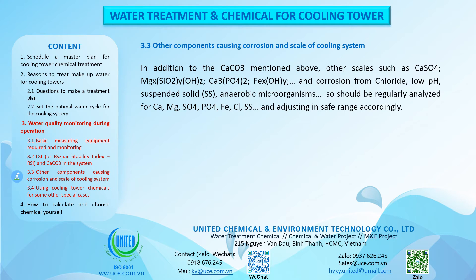Other components causing corrosion and scale of cooling systems: in addition to CaCO3, other scales include CaSO4, MgX(SiO2)Y(OH)Z, Ca3(PO4)2, Fex(OH)y, and corrosion from chloride, low pH, suspended solids (SS), and anaerobic microorganisms. Therefore, Ca, Mg, SO4, PO4, Fe, Cl, and SS should be regularly analyzed and adjusted to safe ranges accordingly.